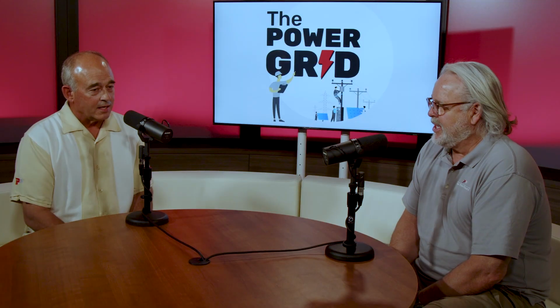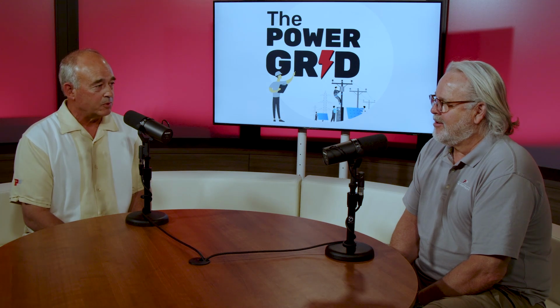So let's talk a little bit about the actual surge suppression device itself. These are engineered to take a fast-moving transient and shunt it to ground. Correct. So how important is the lead length, or the distance that the surge travels before it gets into the surge suppressor? Lead length is very important. And the reason for that is that IEEE, the same people who wrote the Emerald Book, have a standard on mounting the surge protection device. When they measure the voltage that escapes after the surge protection device works, it's called let-through voltage. That's the amount of voltage that escapes and affects the rest of the equipment after the device works. It's not that the unit will fail. They're not designed to fail until the surge reaches an amplitude way above their capacity, but they'll continue working. It's the amount of voltage that escapes after that surge protection device works.